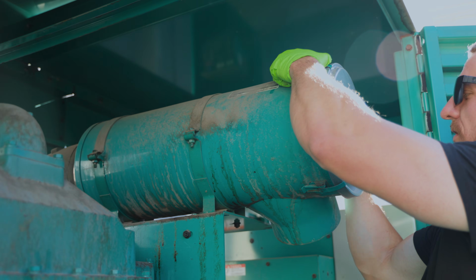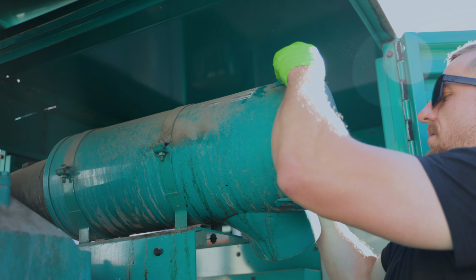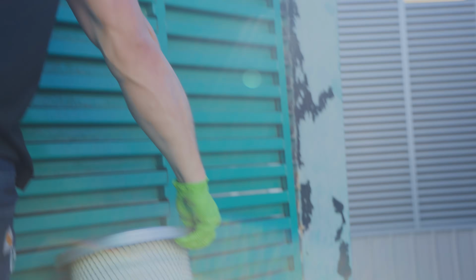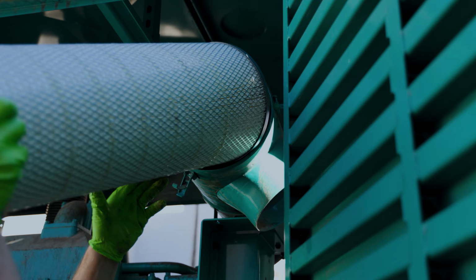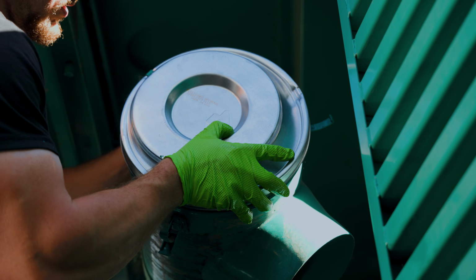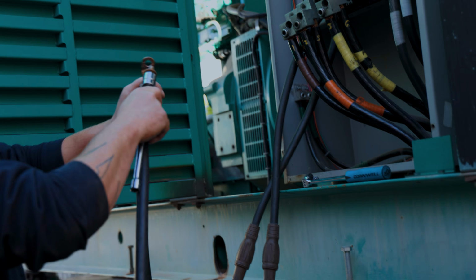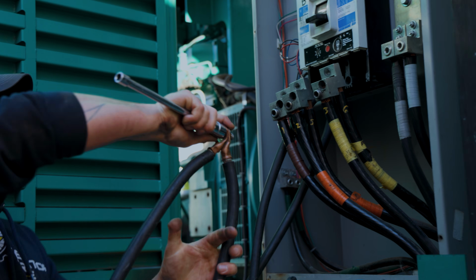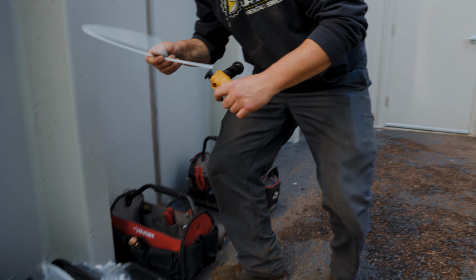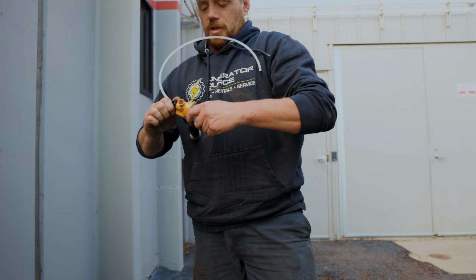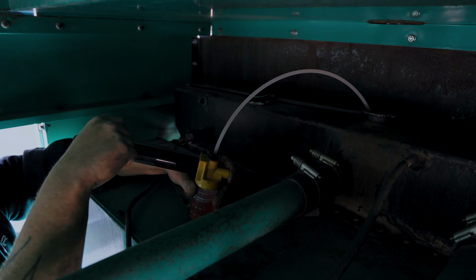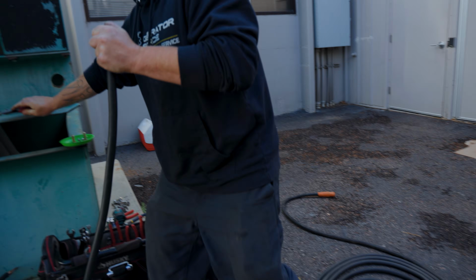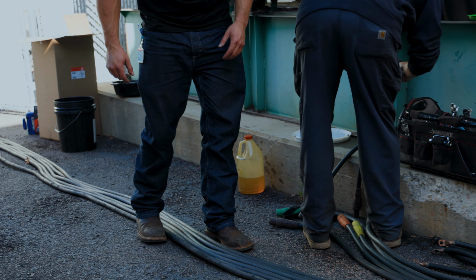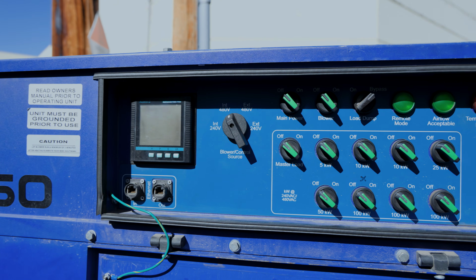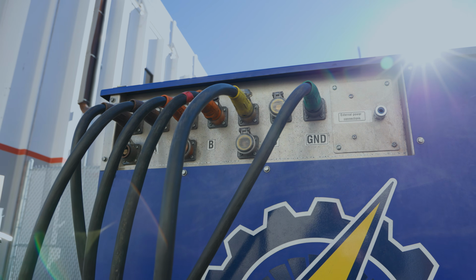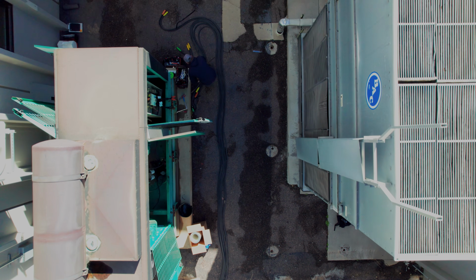Alright. So now we're going to replace the air filter. I'm just trying to make sure it sits pretty flat so we get good contact. Climb up top and get a sample. Depending on the unit, whether it's 480 or 240, you're going to want to swap that on your load bank itself. So this one is a 480, so we'll swap it over to 480 right there. If you don't, you'll blow a fuse on the load bank itself. Ready? Ready guys, here we go.